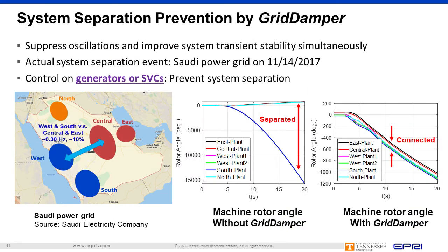Grid Damper can also prevent system separation and improve system transient stability. The Saudi Arabia power grid was forced to separate into two islands on November 14, 2017. The figures on the right compare cases with and without Grid Damper. Based on simulations, Grid Damper implemented on generators and voltage compensators effectively damped the oscillation and prevented the system from separation.